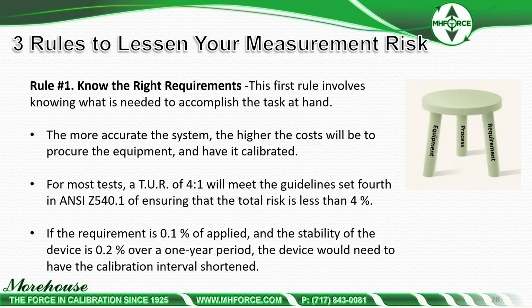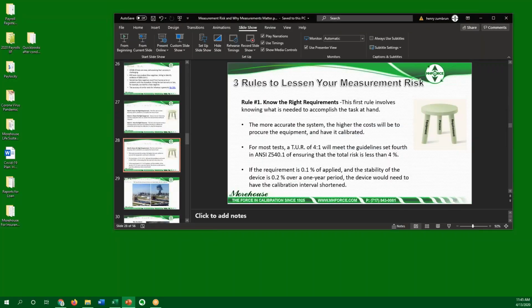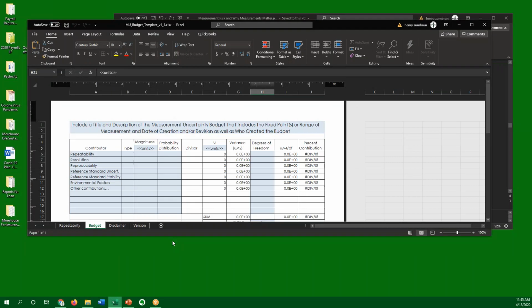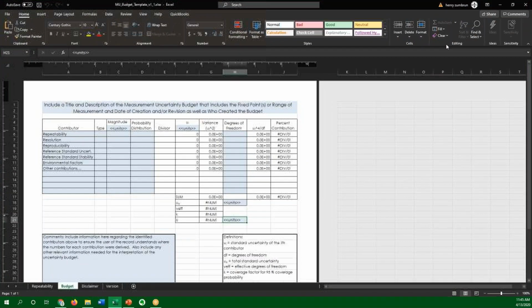And A2LA has an interesting document here. When we look at these, these are the minimums. They come out of R205, which is now going to be replaced. But A2LA has this nice, just really simple to use spreadsheet for calculating uncertainty. It's repeatability, resolution, reproducibility, reference standard uncertainty, and here's the big one: reference standard stability.